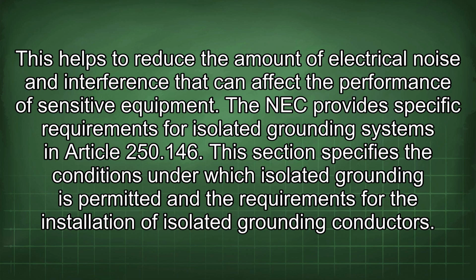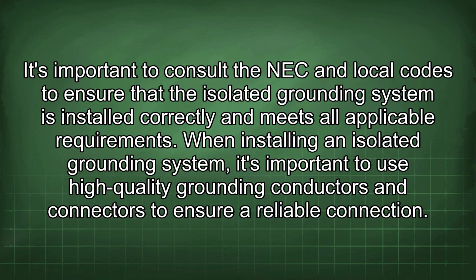The NEC provides specific requirements for isolated grounding systems in Article 250.146. This section specifies the conditions under which isolated grounding is permitted and the requirements for the installation of isolated grounding conductors. It's important to consult the NEC and local codes to ensure that the isolated grounding system is installed correctly and meets all applicable requirements.